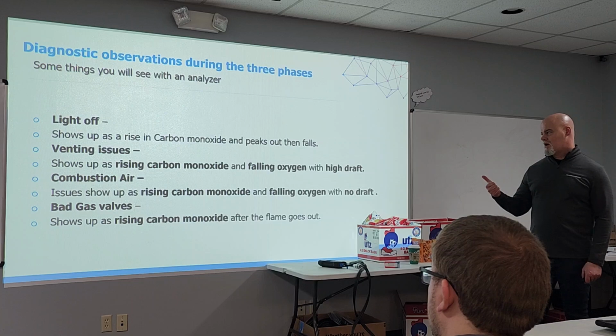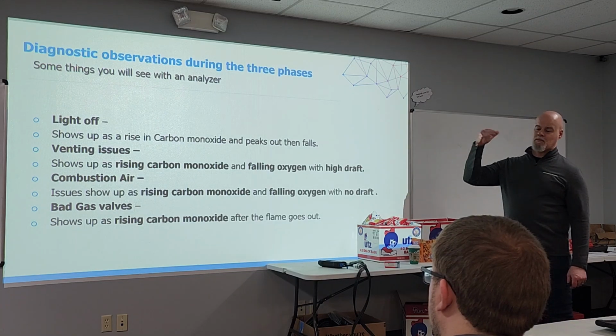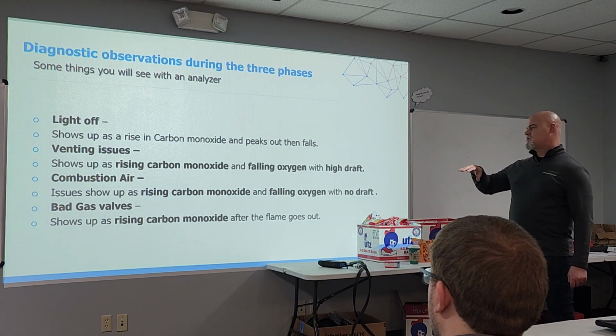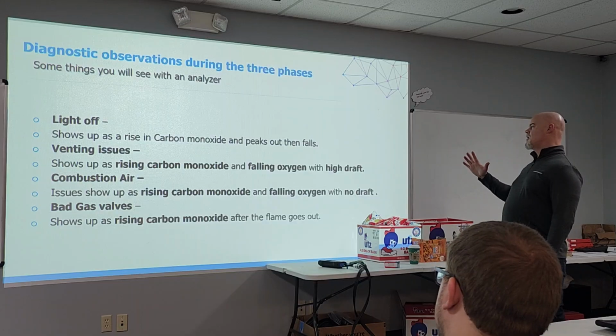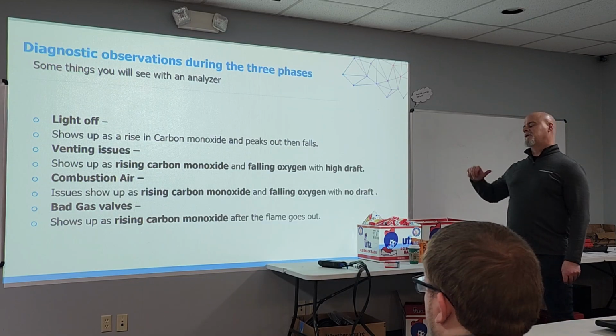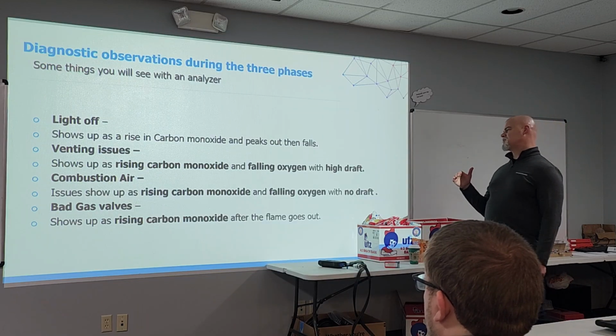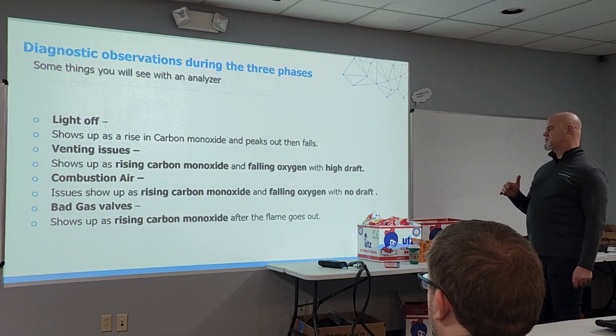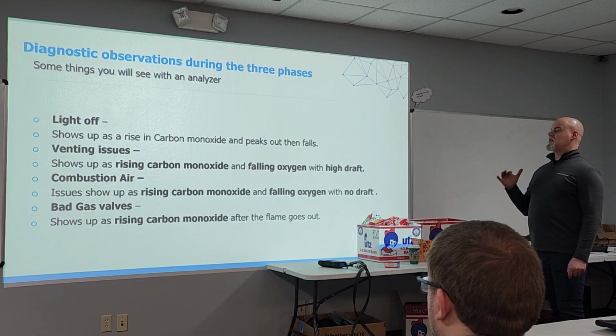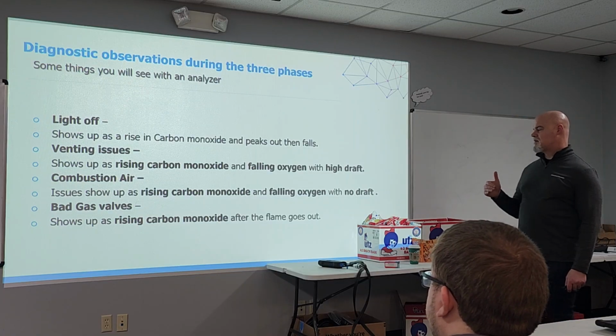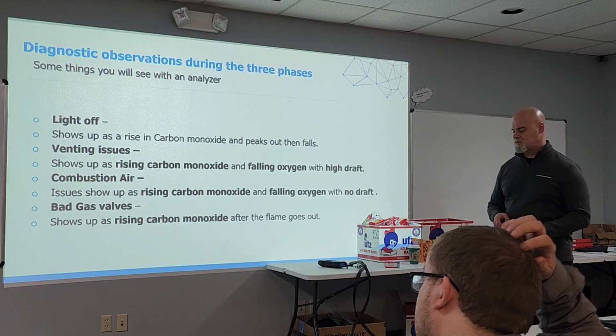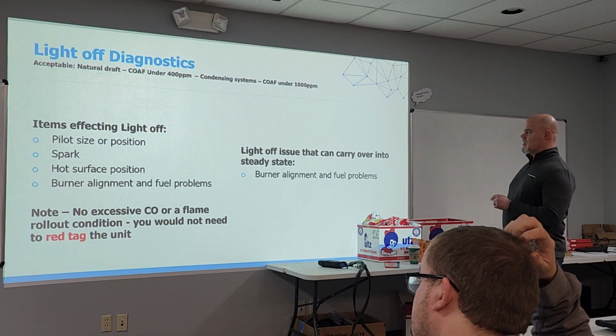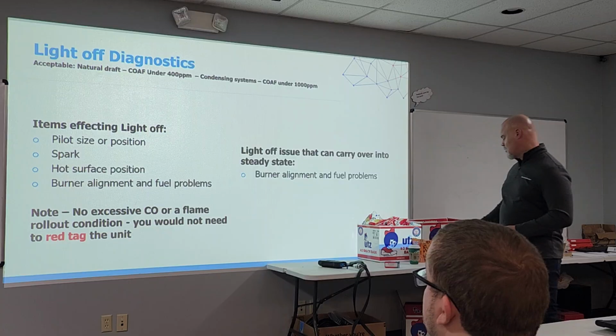Diagnostic observations during these three phases. Light off will show up as a rising carbon monoxide that will peak out and then fall. If you have a venting issue, it shows up as rising carbon monoxide with falling oxygen and high draft. If you have a combustion air issue, it shows up as rising carbon monoxide, falling oxygen with no draft. And if you have bad gas valves, it shows up as rising carbon monoxide after the flame goes out. Light off diagnostics, very important.